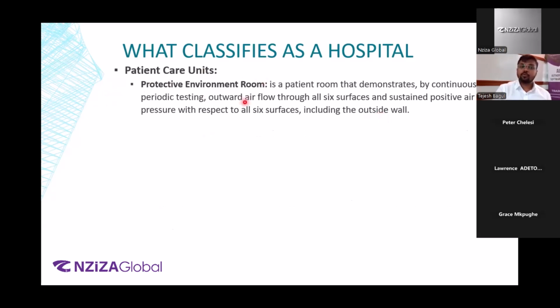Next, talking about the protective environment rooms. These rooms are usually constantly monitored. This was something that happened during COVID times, where we needed constant monitoring of the rooms, making sure the contaminant levels don't spike up, and that spike giving rise to even more COVID patients, right? So as I mentioned over here, there are six surfaces, right? Four walls, one floor, and one ceiling. All of the six surfaces are to be maintained at positive pressure. What is positive pressure? It concerns the air that you are bringing into the room, right? Everyone knows the unit for volumetric flow rate, CFM. Have you guys heard about CFM? Liters per second, right? So that is all volumetric flow rate. So the volumetric flow rate needs to be positive. The CFM needs to be positive. The pressure needs to be positive.